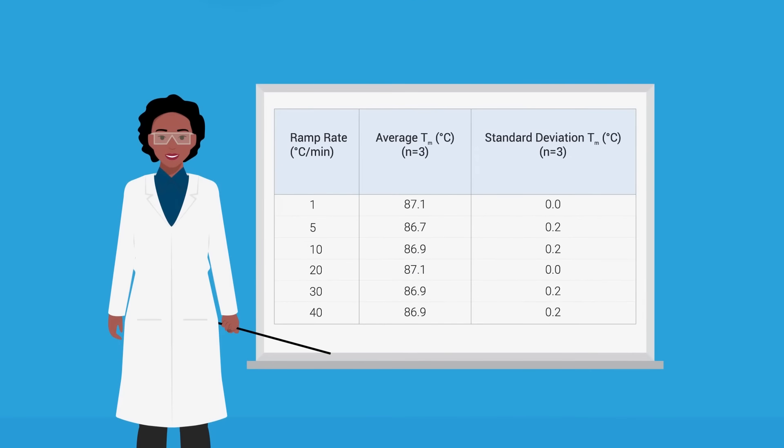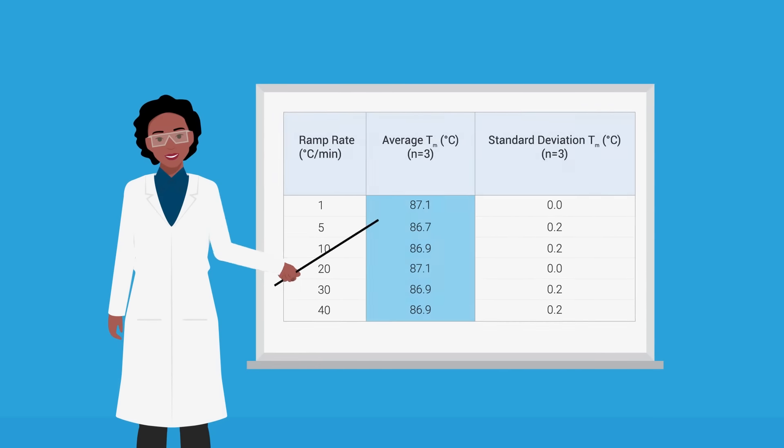Alice tested temperature ramp rates ranging from 1 degree per minute to 40 degrees per minute. The melting temperatures of her oligonucleotide were within 0.4 degrees of each other regardless of ramp rate, so she's confident that her data accuracy is not affected by the shorter assay time.